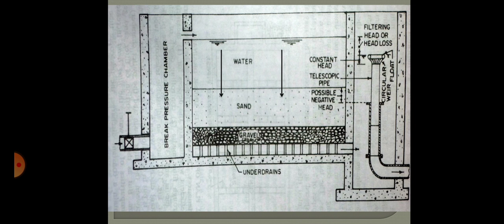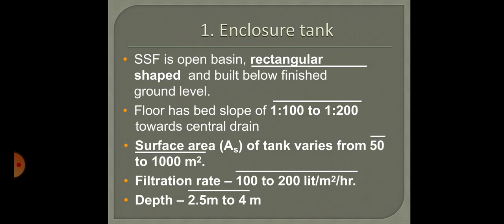A typical slow sand filter is an open basin, rectangular in shape, normally built below ground level. The watertight basin is constructed in masonry — either stone masonry or brick masonry. The floor of the tank has a bed slope of 1:100 to 1:200 towards the center, sloping from both sides. The surface area of the tank varies from 50 to 1000 square meters, the filtration rate is around 100 to 200 liters per square meter per hour, and the depth of the tank is normally between 2.5 to 4 meters.